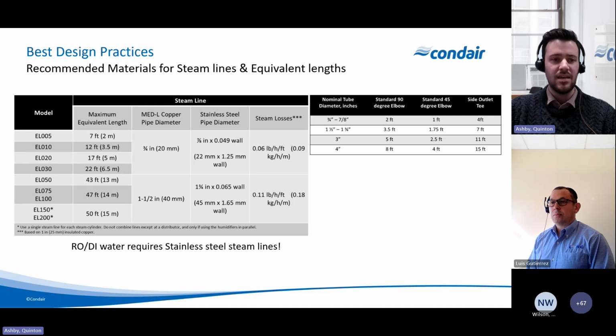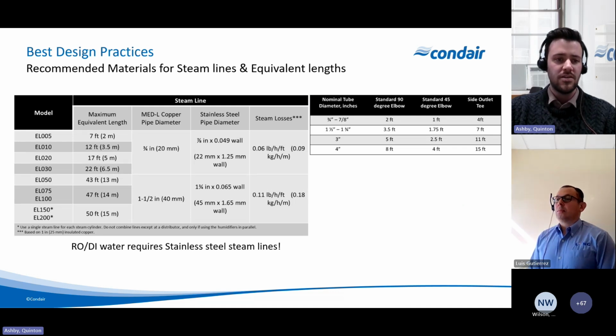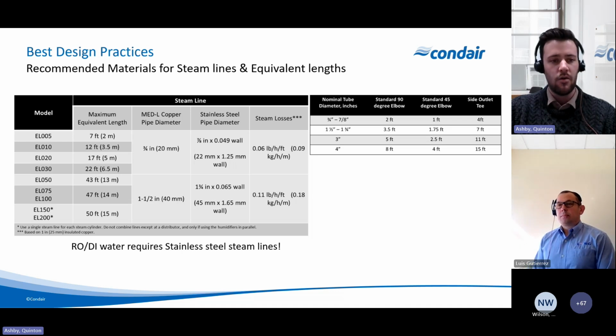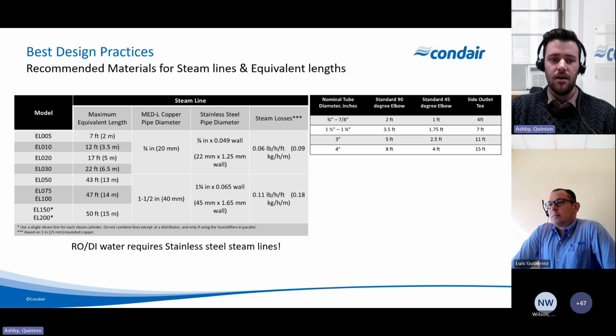So if we look at, this is an EL steam line maximum equivalent length chart. So as you can see, as the model goes higher, so the higher pounds per hour, we can actually go longer with the steam line. One thing to note is that this is a maximum equivalent length. So equivalent length actually takes into account back pressure from elbows and fittings into that length. So it's different than the linear length. So that's something that we need to consider.